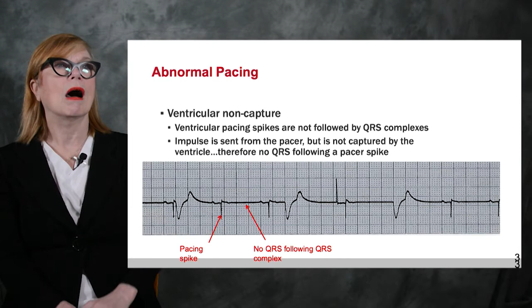So we're going to turn all the way up to 20, and that's the highest we'll ever go. At 20, can we capture the ventricle? And then we're going to turn down slowly until we see failure to capture, and we step just above failure to capture in order to capture the ventricle. Now, non-capture means spike to spike to spike is absolutely on time, but we don't have a ventricular response. So first, before you ever say non-capture, you must be sure spike to spike to spike equals the rate that you set on your pacemaker.